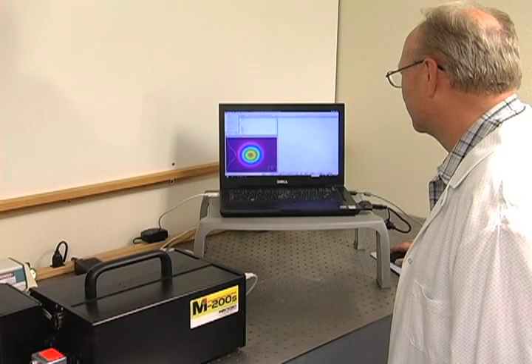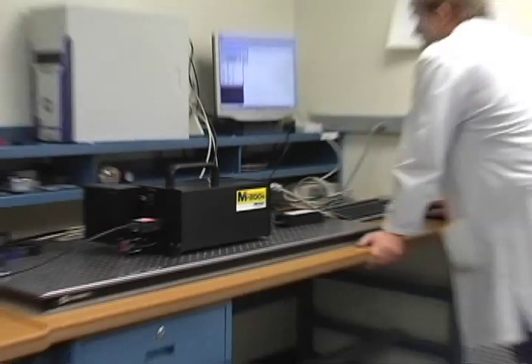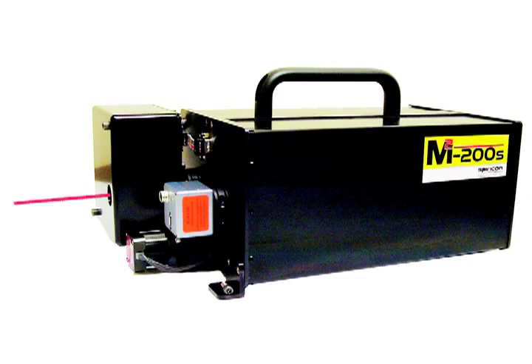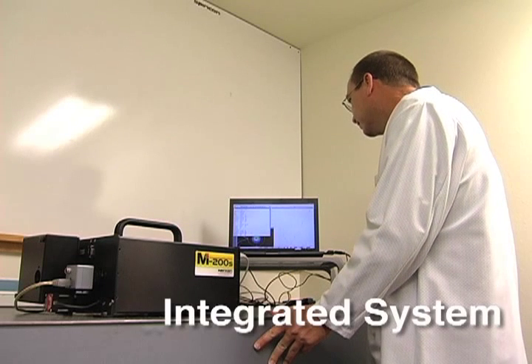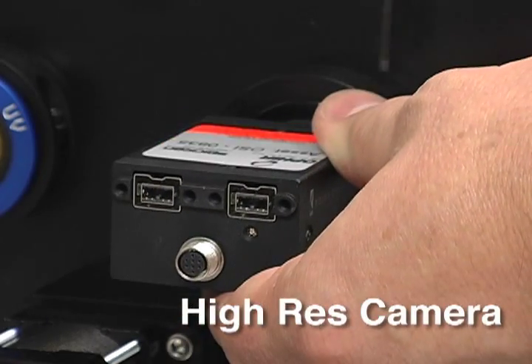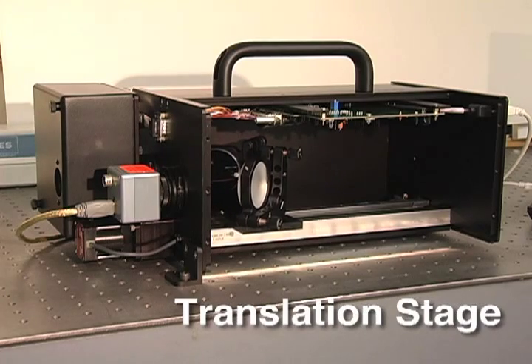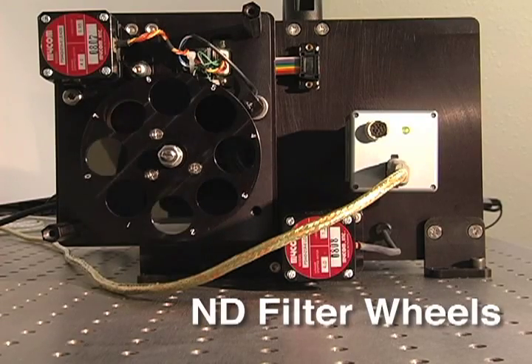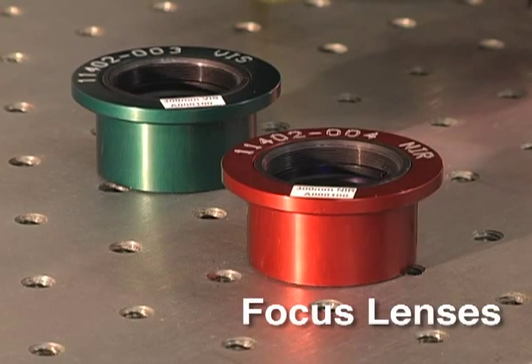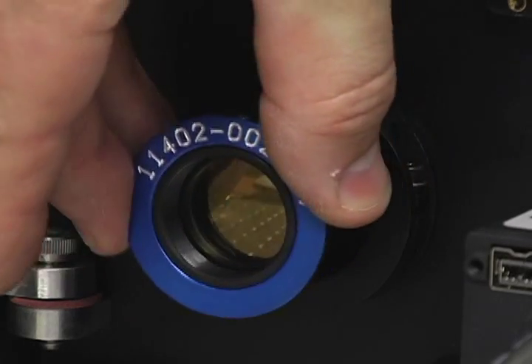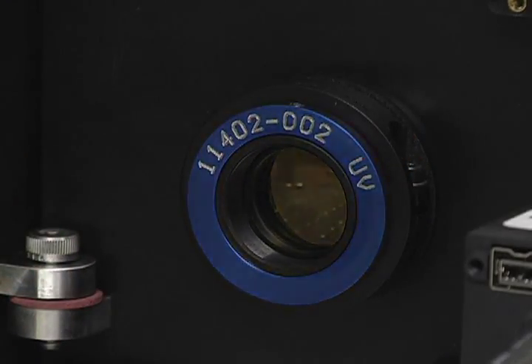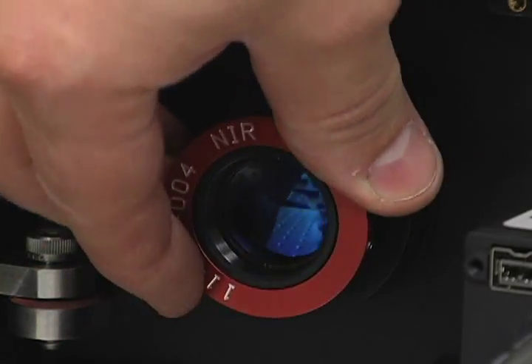Performing an M-squared measurement with an Ophir Spiricon beam propagation analyzer such as the M-squared 200 and M-squared 200S is quite simple. The systems are completely integrated, consisting of a high-resolution camera, automated optical train with translation stage, two automated ND filter wheels, and distortion-free focusing lenses. The focusing lenses are interchangeable, allowing the user to change wavelength regions without disassembling the system.